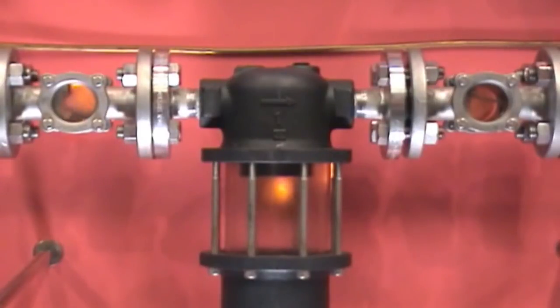enabling clean, dry steam to be fed to your system at maximum thermal efficiency. They are capable of removing 99% of particulate entrainment 10 microns and larger over a wide range of flows.